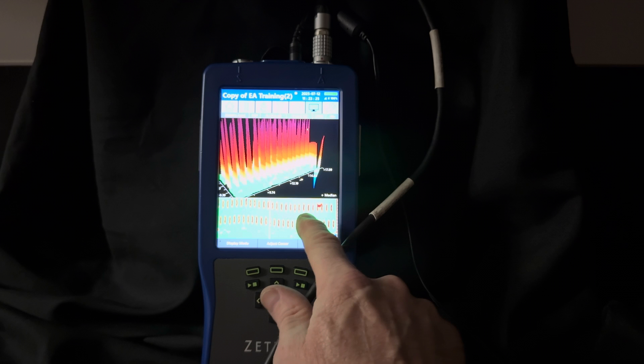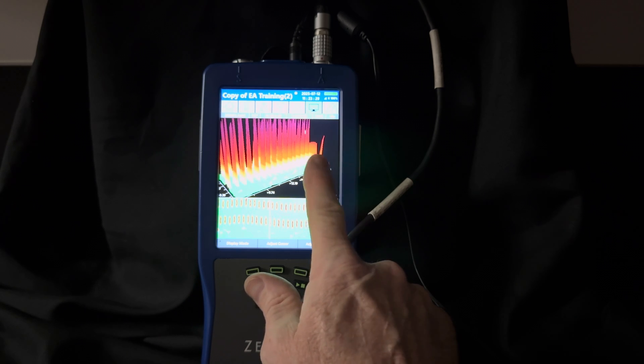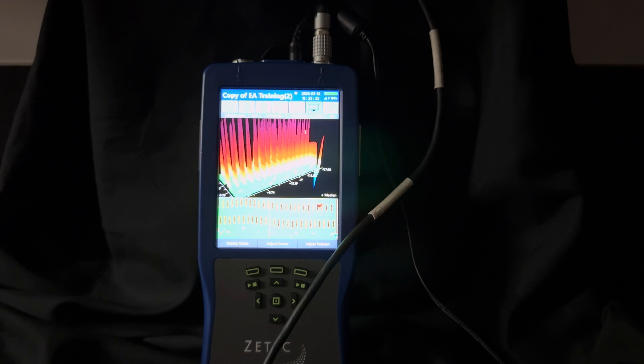In your training for eddy current testing and data analysis, you may have heard the term high repetition signals. If you were doing a tubing exam, tube support plates would be high repetition signals. That means they happen often.